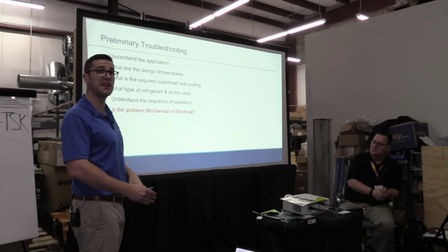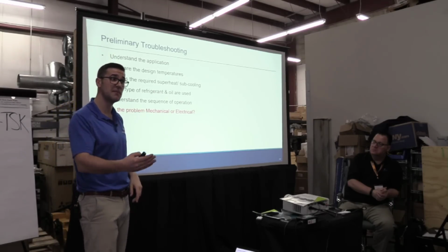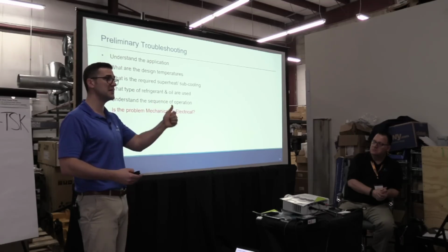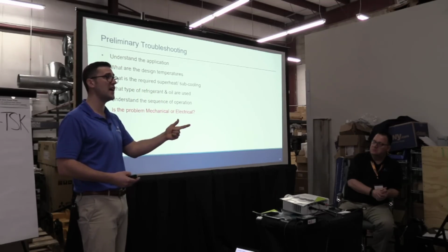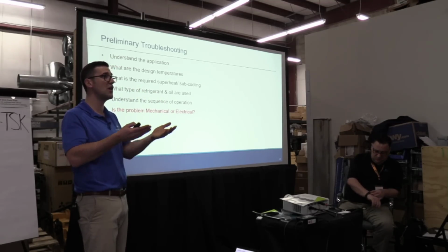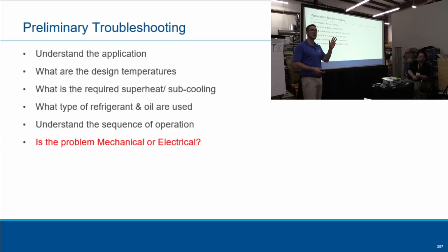Understand the sequence of operation. When you start understanding the sequence of operation of a system and how it runs, okay, the thermostat closes, the solenoid valve opens, the low pressure starts to rise, the low pressure switch closes, the contactor energizes, pulls in, and the compressor starts. You want to know this stuff. Understand the system you're working on and how it works. It's going to make you a way better technician in the field.